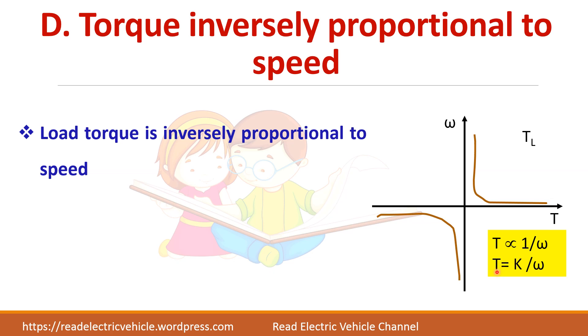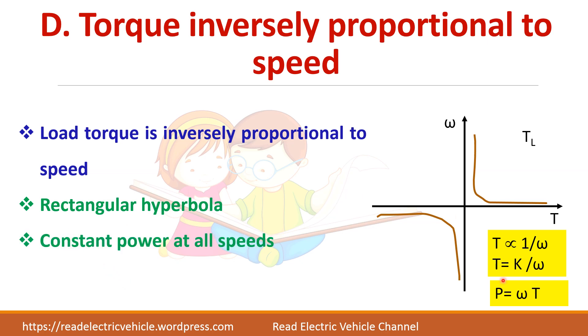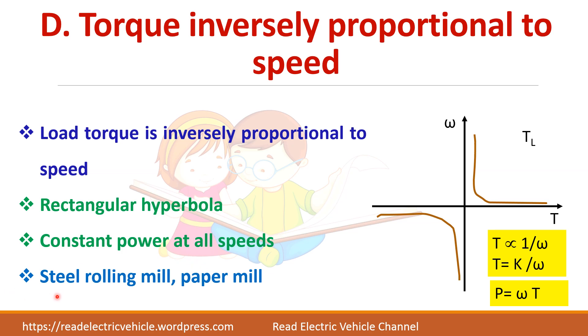The fourth type is torque inversely proportional to speed, giving a rectangular hyperbola. Since power equals ω × T, the power is constant in these loads — so it is called a constant power load. This is found in steel rolling mills and paper mills.